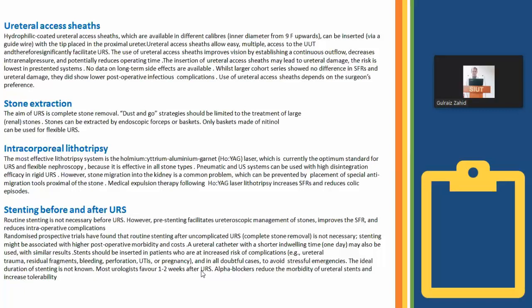Stone extraction. The aim of URS is complete stone removal. Dust and go strategies should be limited to the treatment of large renal stones. Stones can be extracted by endoscopic forceps or baskets. Only baskets made of nitinol can be used for flexible URS.